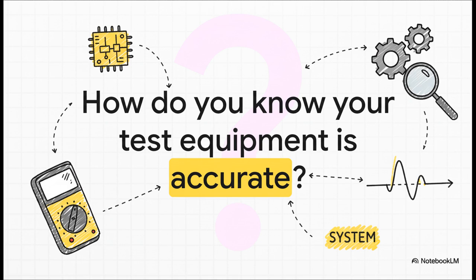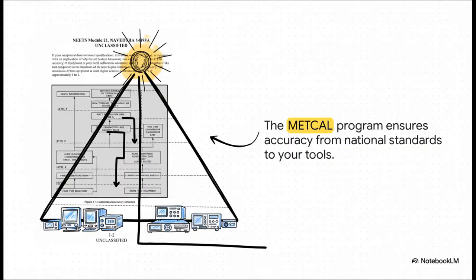You pick up a meter, you take a reading, how do you actually know that number on the screen is the real deal? Are you just supposed to cross your fingers and hope for the best? No way. There's a whole system designed to prevent that, called the Metrology Calibration Program, or METCAL for short.